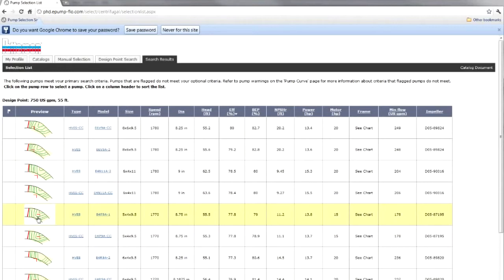So that could be a great selection. But you also notice that I'm only operating at 77.8% efficiency. So even though I'm at my best efficiency point, I'm actually less efficient than I was with the pump that's operating to the left. Why? Because it's a smaller pump.